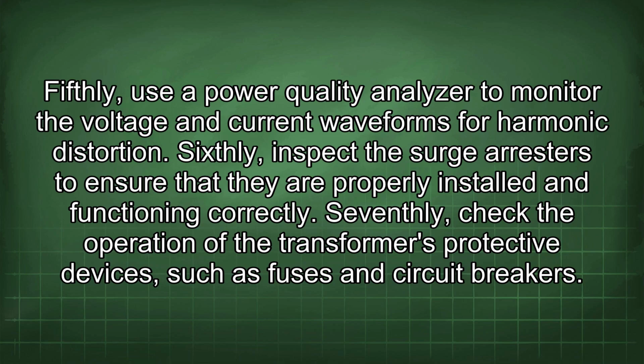Fifthly, use a power quality analyzer to monitor the voltage and current waveforms for harmonic distortion. Sixthly, inspect the surge arresters to ensure that they are properly installed and functioning correctly. Seventhly, check the operation of the transformer's protective devices, such as fuses and circuit breakers.